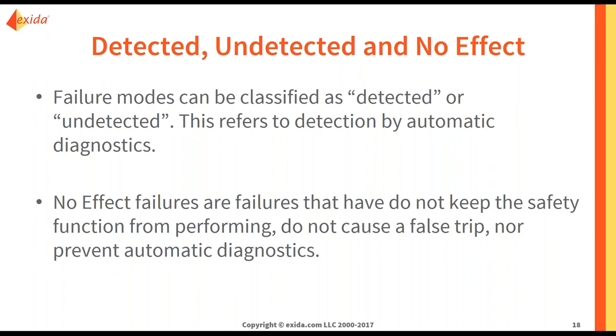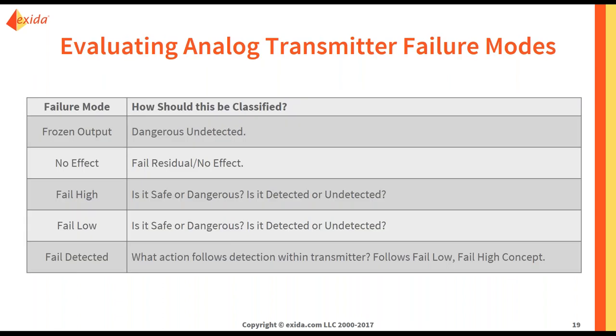So how do we apply these in your system? Your frozen output is very often dangerous undetected. You are not going to know that you have an unhealthy signal, because it is still within the healthy range. In this case, it is keeping your safety instrumented function from responding to the hazardous scenario. So it is dangerous, and it is undetected. No effect is a case where your signal is less accurate — perhaps it is noisy — but it is not keeping you from responding to the hazardous scenario, and it is not tripping your plant.